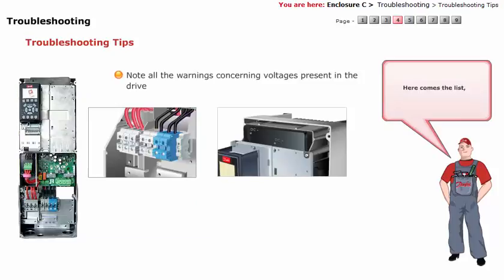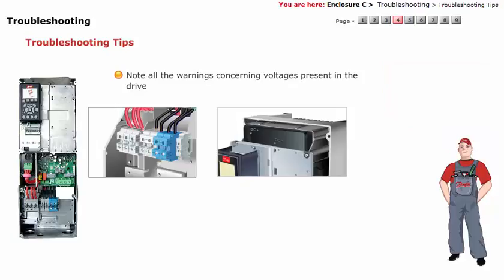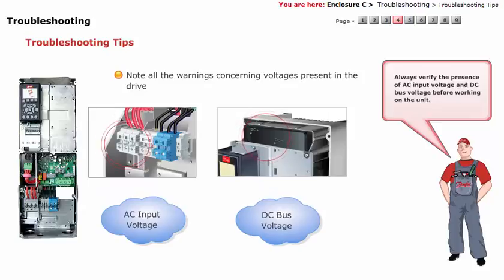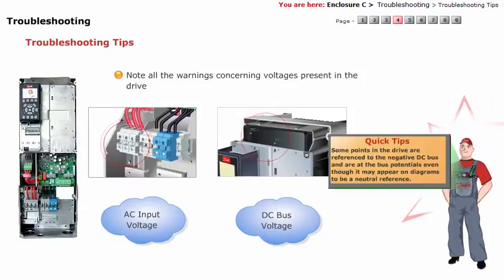Tip 1: Note all the warnings concerning voltages present in the drive. Always verify the presence of AC input voltage and DC bus voltage before working on the unit. Some points in the drive are referenced to the negative DC bus and are at bus potential, even though it may appear on diagrams to be a neutral reference.